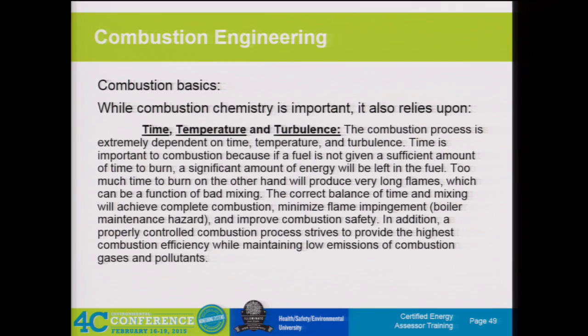So this time, temperature, turbulence basics are important to keep in mind. The correct balance of time and mixing will achieve complete combustion and minimize flame impingement. If we have too much time, we can get an elongated flame that's going to not be controlled within the combustion area that we want in the firebox.